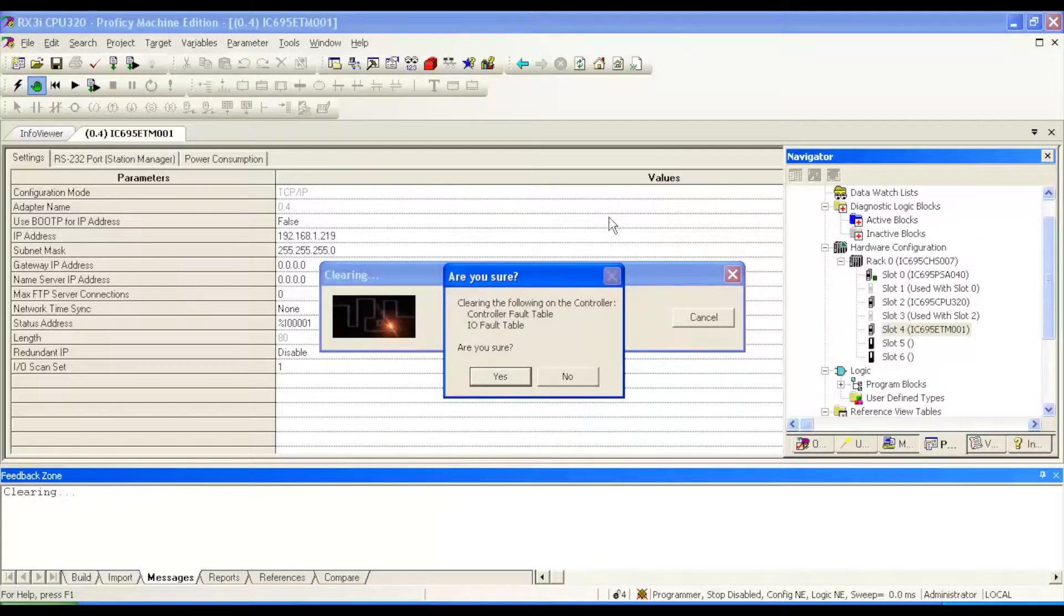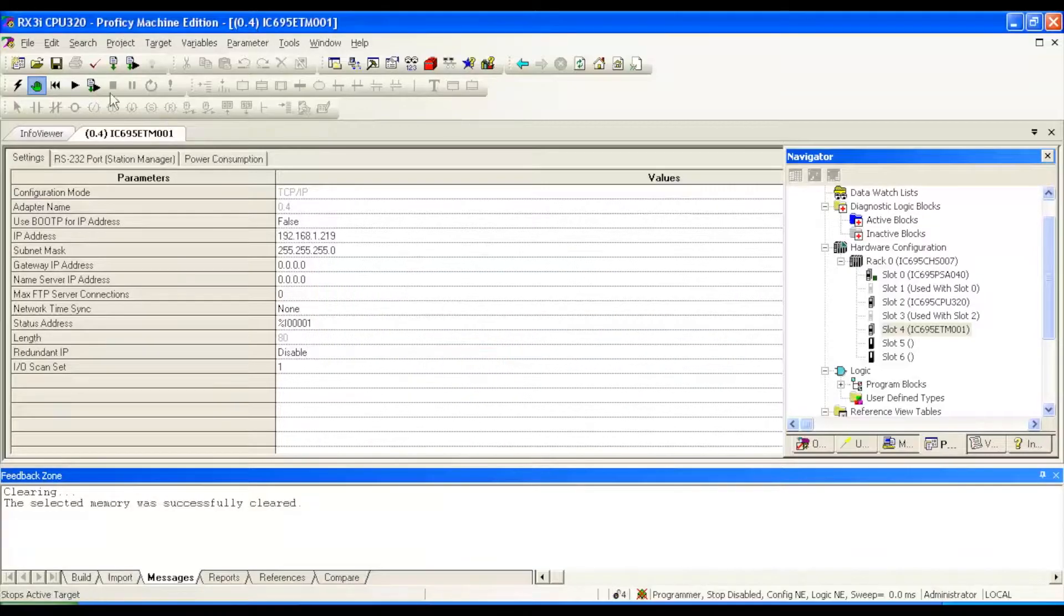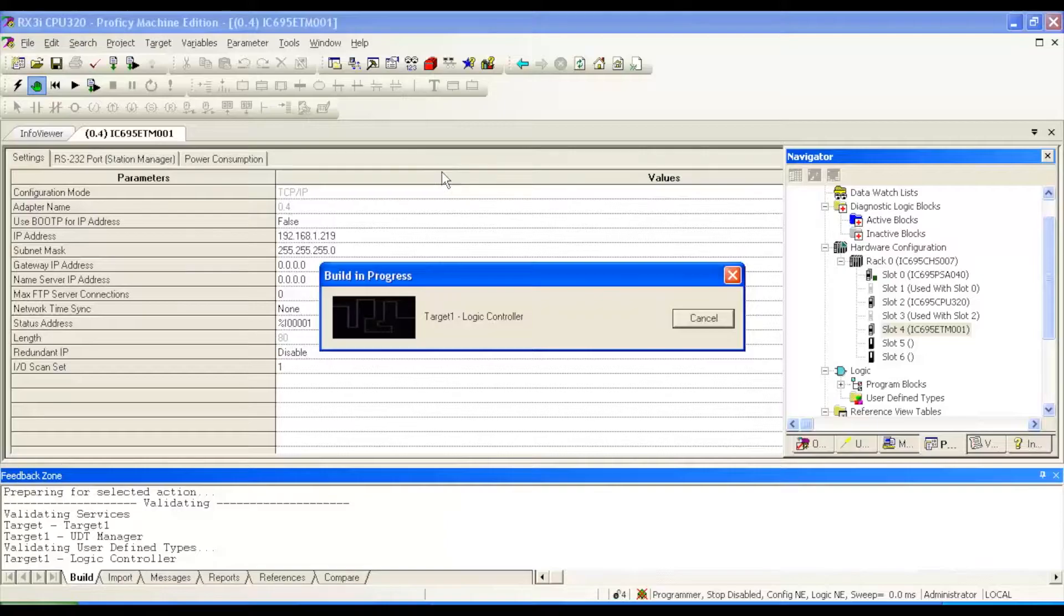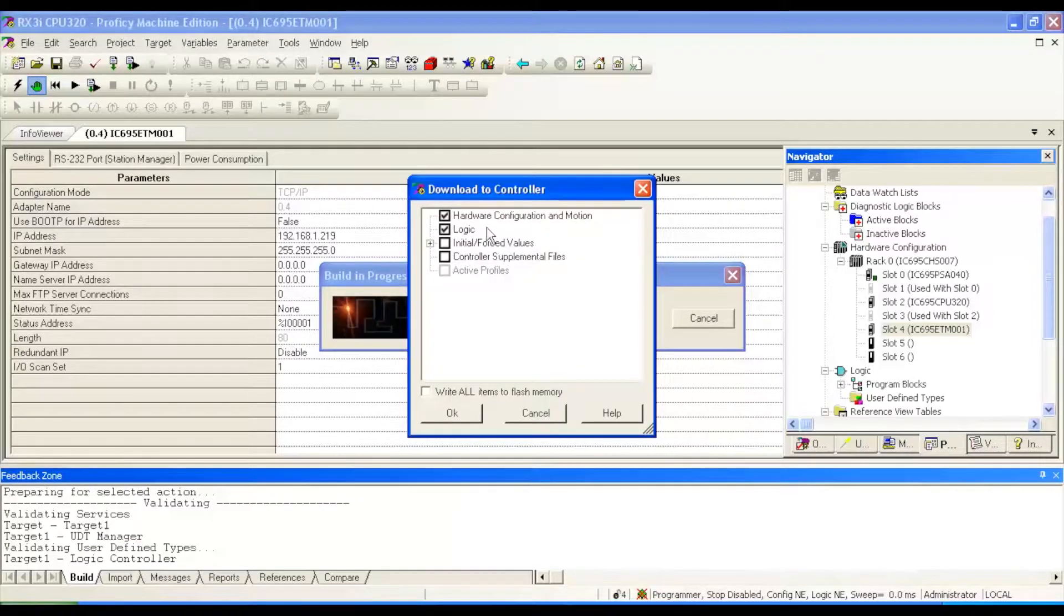Then download and run. The first thing it's going to ask us is what exactly do we want to download to the processor. It'll be the first two selections, configuration and logic. Hardware configuration and motion and logic. We don't want to write anything to the permanent flash memory or anything else.